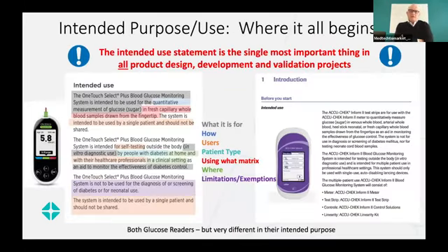So the whole project of all diagnostic projects, all medical device projects should start with an intended use statement. This is a really important document, and you can see this if you open up a pack of paracetamol or open up any diagnostic test, and you will have in the instructions for use, probably on the first or second page, an intended use statement.